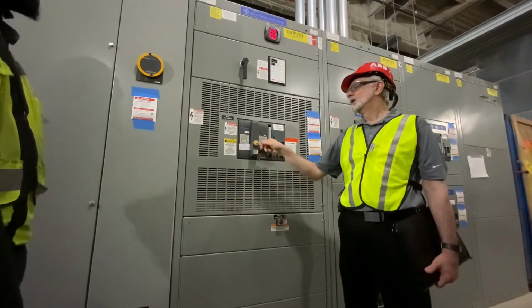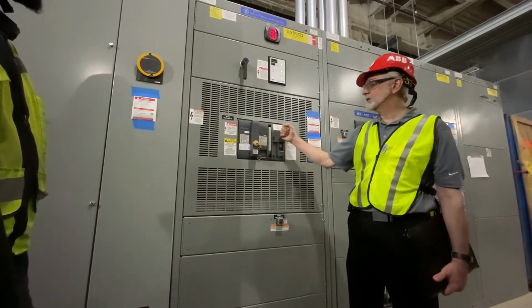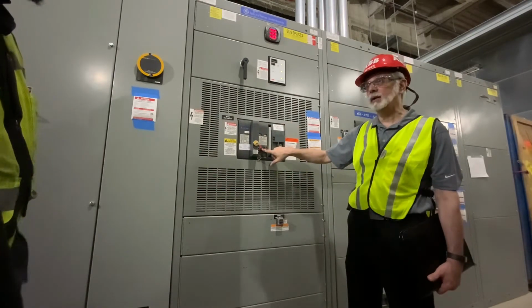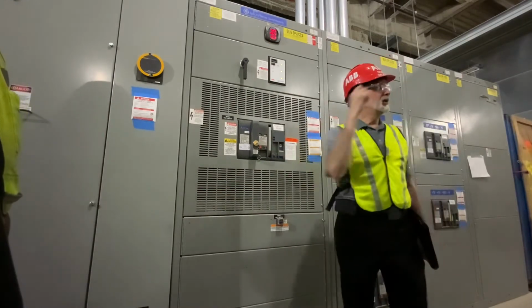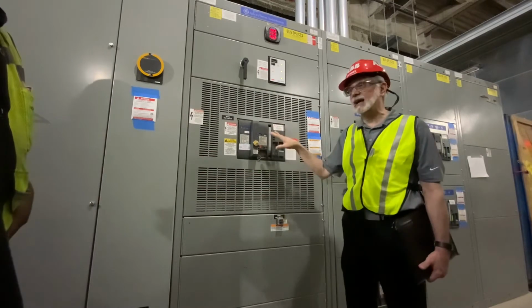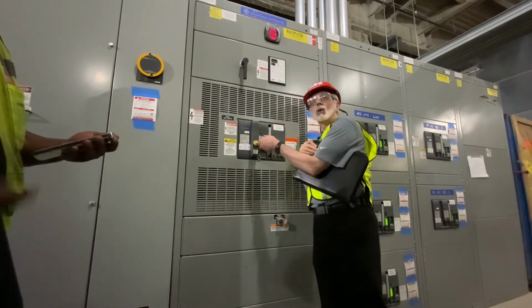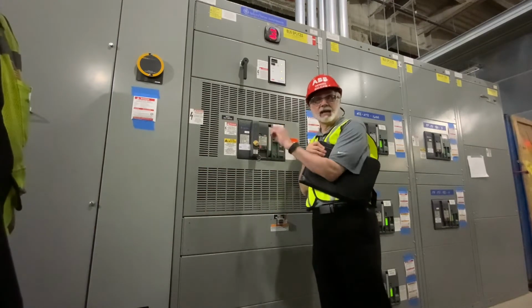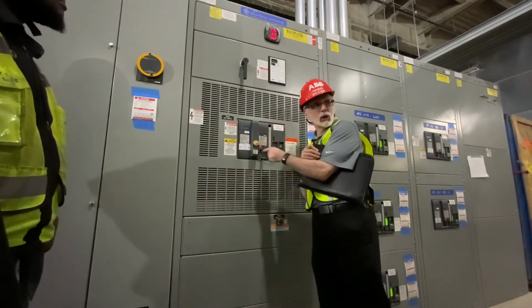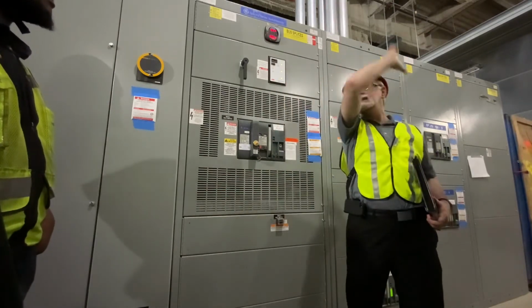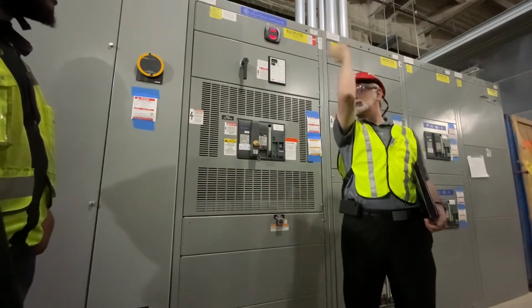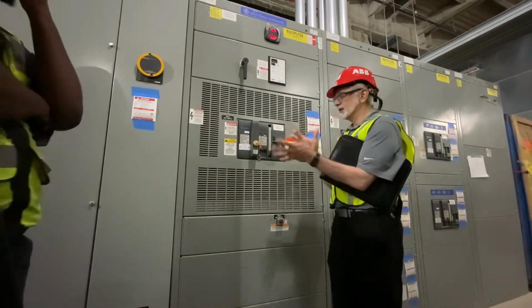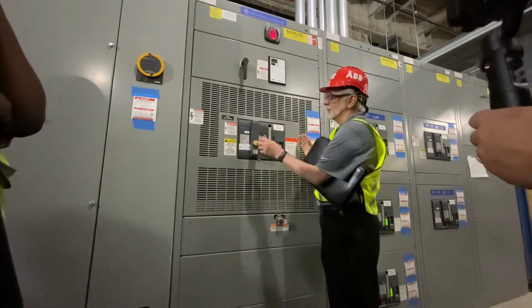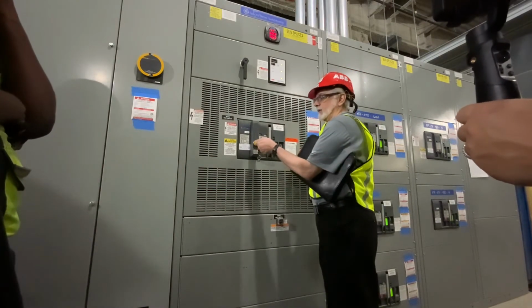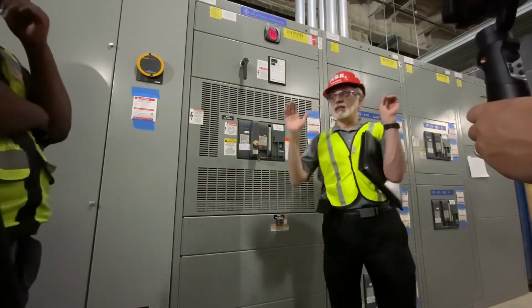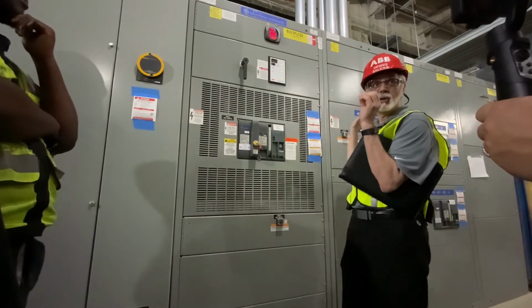You would have to take the key and open the breaker here, to the open position. The key would then be released. You would walk over to the tie breaker, which looks just exactly like this. You would stick the key in there and rotate it, and the key would become captive, so you can't take it out. Then it would give you the ability to close the tie breaker, and you would be single-ended the lineup from the good source. So in that particular case, I would first open the breaker, rotate the key, and remove it. This whole substation side would be dead, with no power flowing through it.